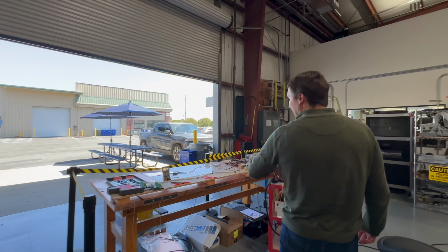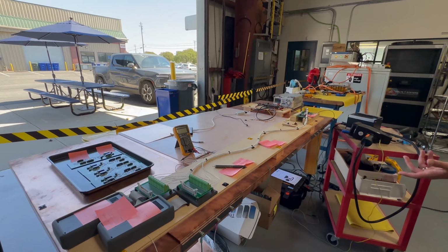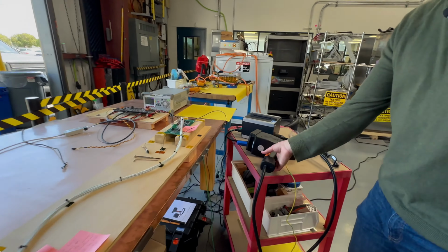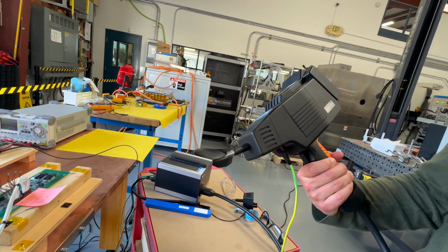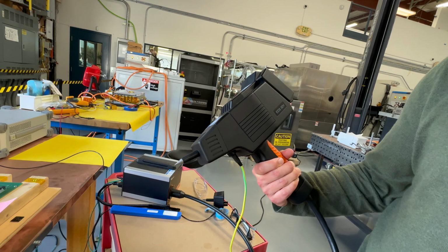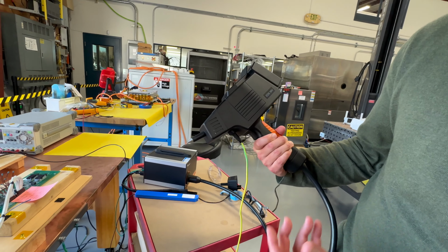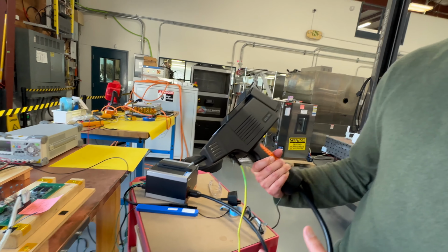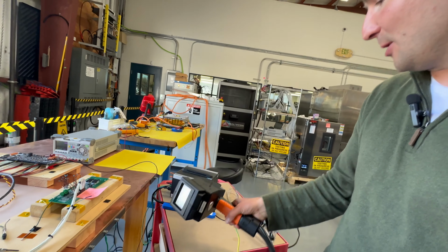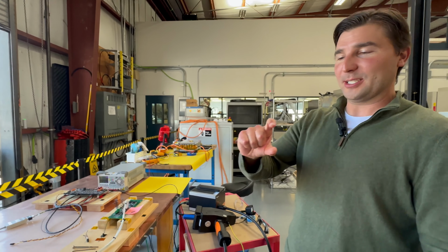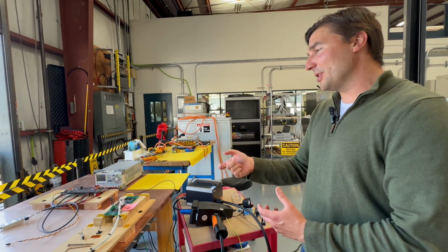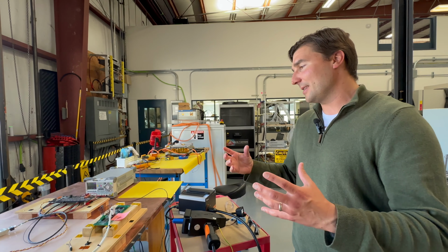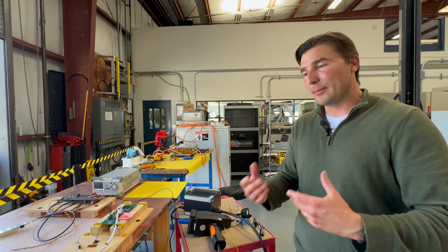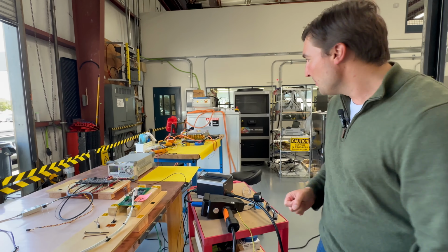So over here, we're doing some ESD testing. This is basically electrostatic discharge. We're taking an ESD gun. You can see what this is. This generates a lot of static electricity, the same way that walking across a dry carpet would. So don't touch the end of it, especially when it's powered, but it can generate sparks about that big. And so we zap the boards and the electronics to make sure that they work even in an environment where sometimes you get electrostatic discharge.